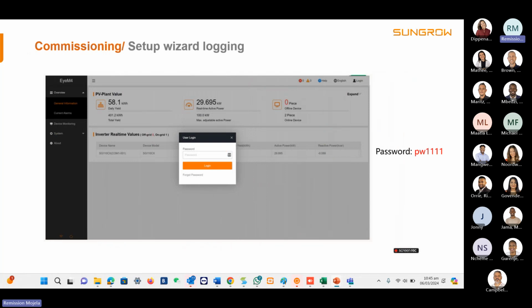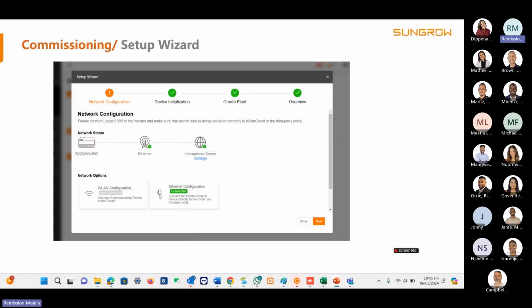PW1111. So the moment you log onto that particular device, it will ask for user login. You just have to use the pw1111, which you can change after commissioning the plant, if you need to, but it's easier to leave it like this because everyone remembers it. Basically, if you ask a Sungrow person to have a look at your plant, they can also access it, just in case you misplace or forget the password that you changed it to. So now the password will be pw1111, and then it will run you through the setup wizard automatically.